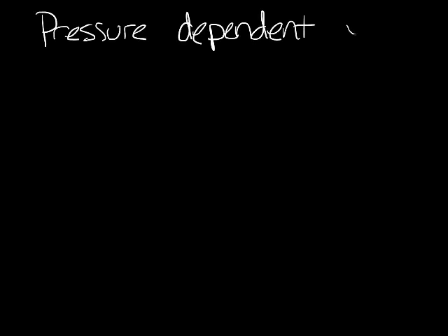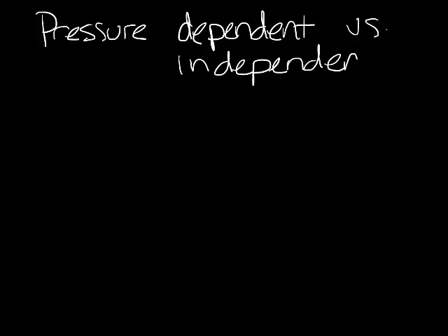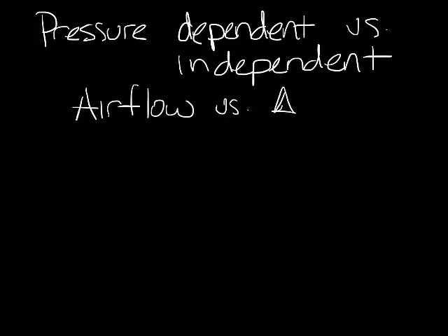Pressure dependence and pressure independence has to do with how airflow through a VAV box reacts to changes in pressures in the system. As the name implies, the amount of airflow you get in a pressure dependent box depends on how much pressure you have.